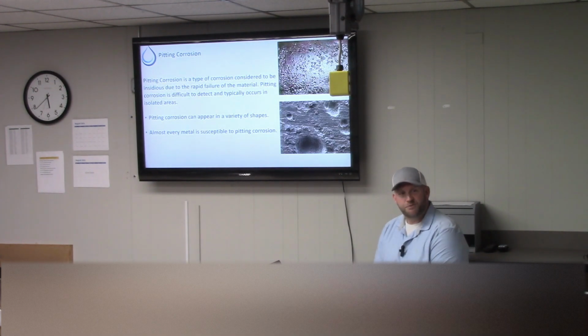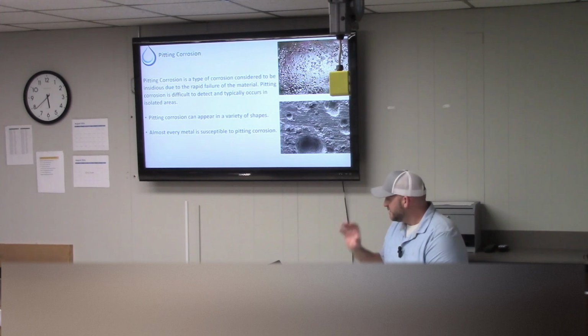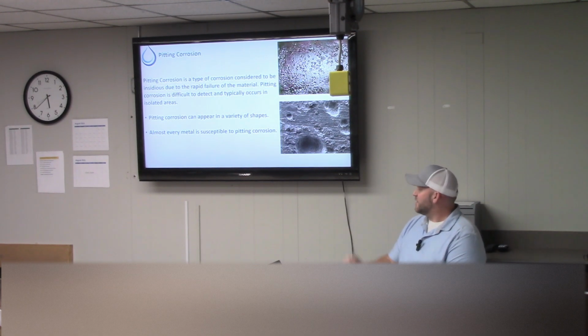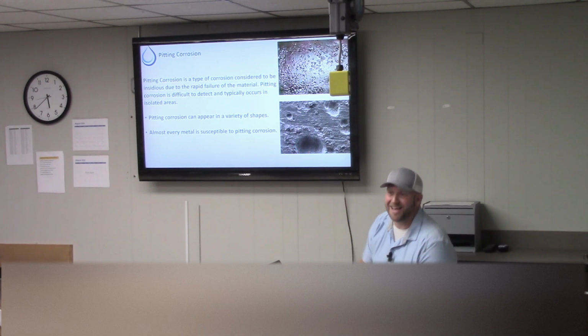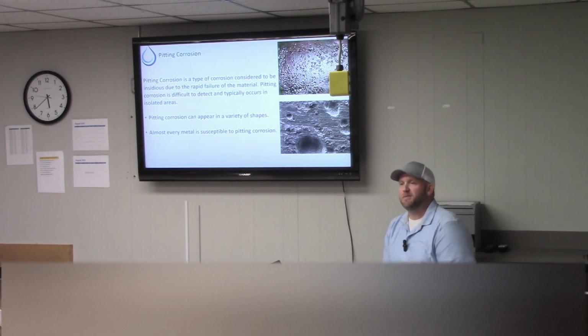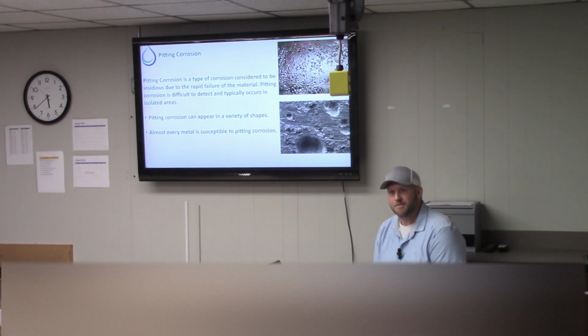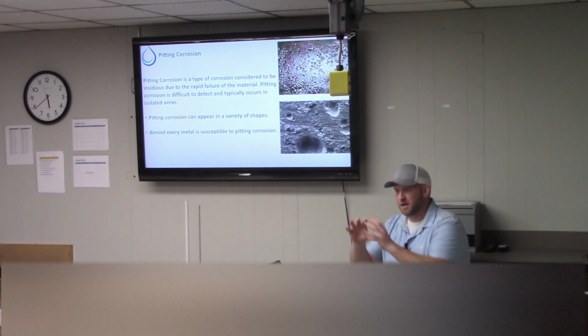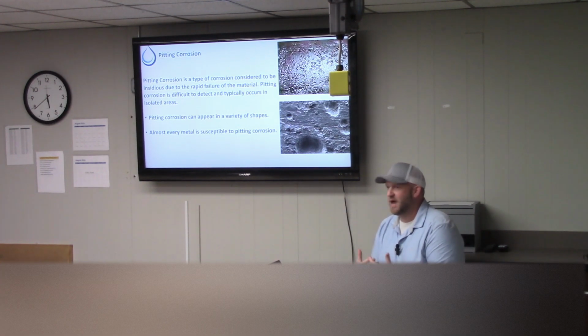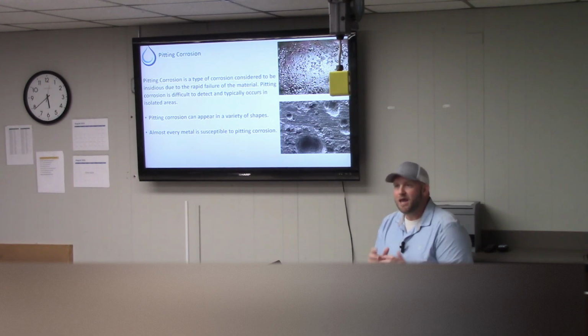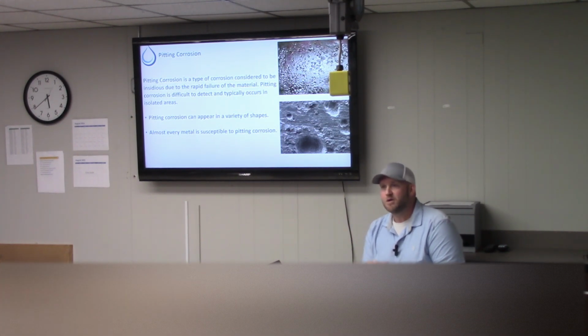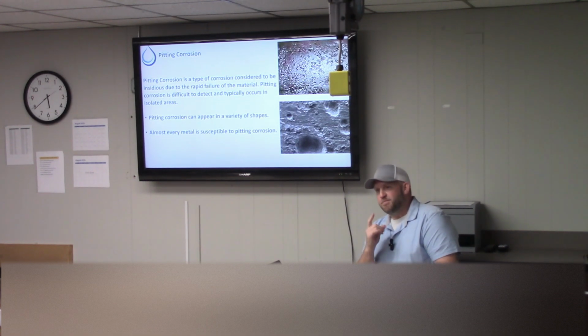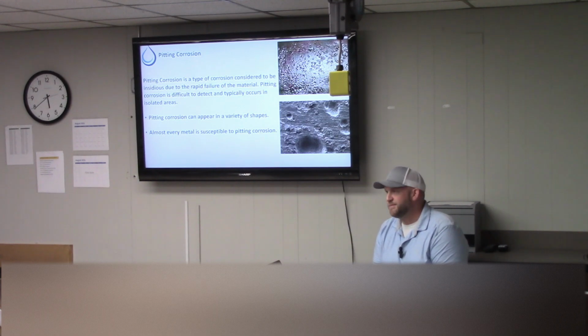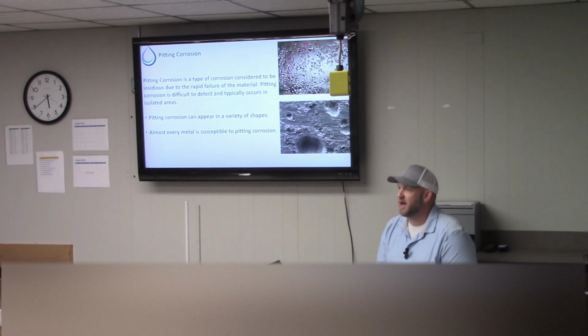Pitting, on the other hand, is the first of our insidious, terrible types of corrosion. It gets front stage because it's hard to detect. Oftentimes it's localized, found in an elbow or a portion of the system, not the entirety of it. If it's pitting in a small localized area, it dilutes the iron or whatever metallurgy is there, making it hard to detect through testing. Pitting corrosion usually bites you right in the rear end, and you find it, hopefully at inspection intervals, before it causes an unplanned outage.